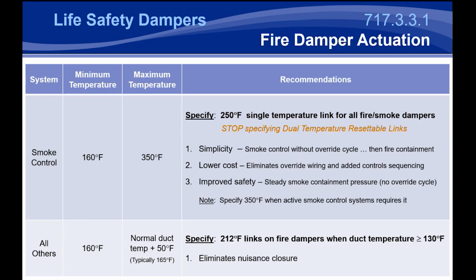I also recommend specifying the damper to 250 or 350 to match the temperature certification of that smoke control system. And the same thing goes into effect really for all fire dampers or fire smoke dampers. The reason I say that is there's a cost savings to be had if your system is only designed to operate at 250 degrees. With that system, if the damper will never see 350 degrees, but you certify that damper to 350 degrees, you actually have to test to make sure that damper will operate at a higher temperature. And that equates to typically a higher operating cost and a higher torque cost for the motors for these dampers.